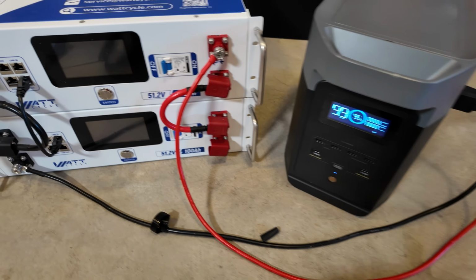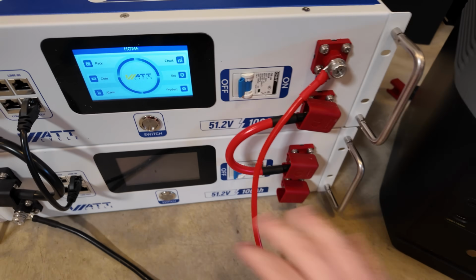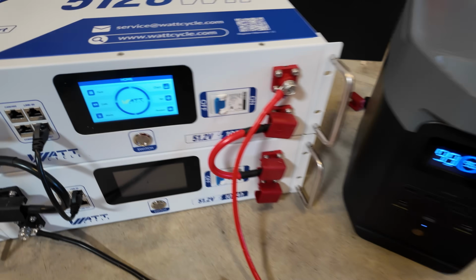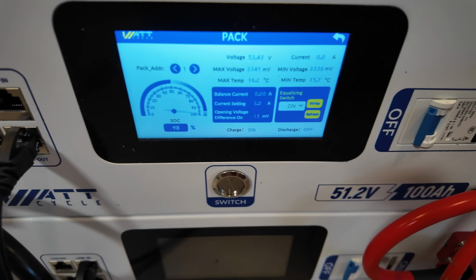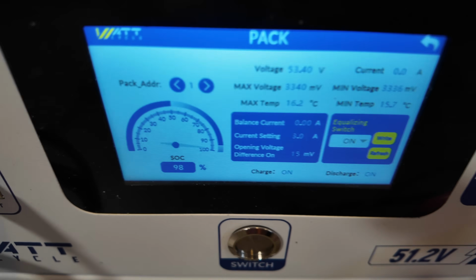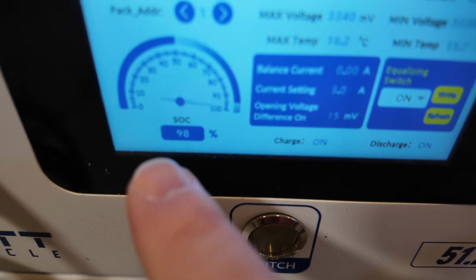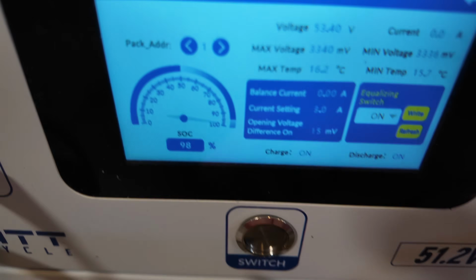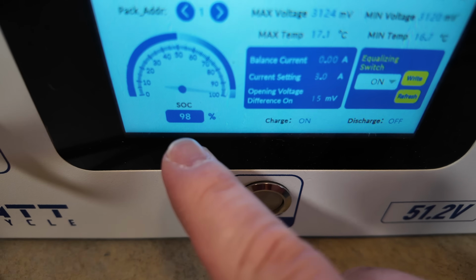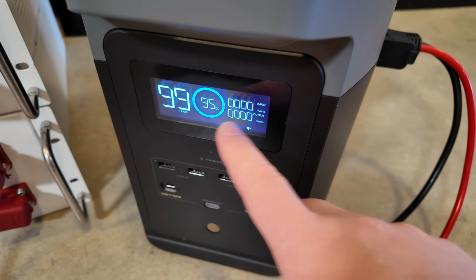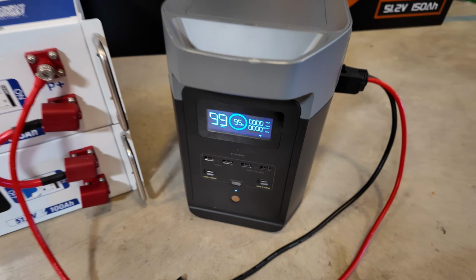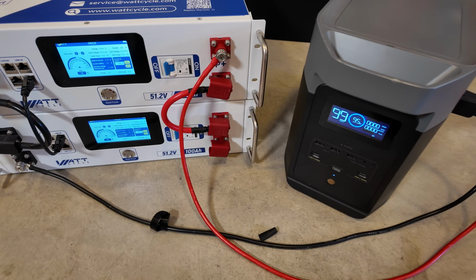The one other thing you want to check prior to flipping any breakers to complete the circuit between the two units is you want to just make sure that your battery is very close to the same state of charge. So you can see these batteries here are 98%. The bottom one here is 98%. And you can see the EcoFlow is 95. That should be close enough to not have a giant surge of power between the two.